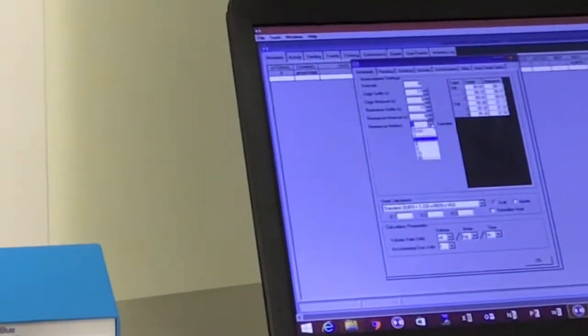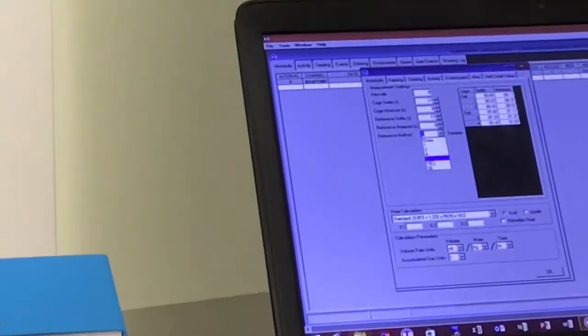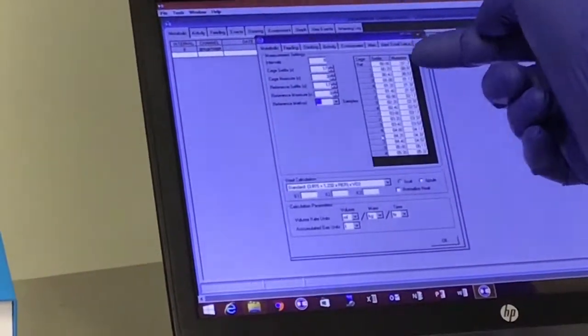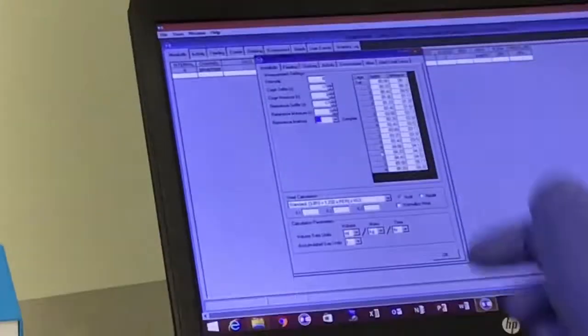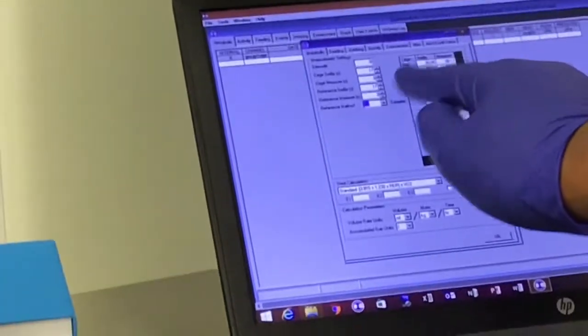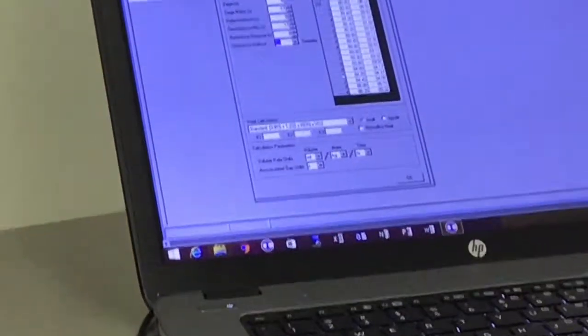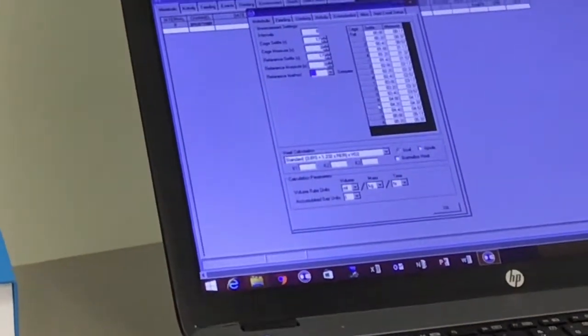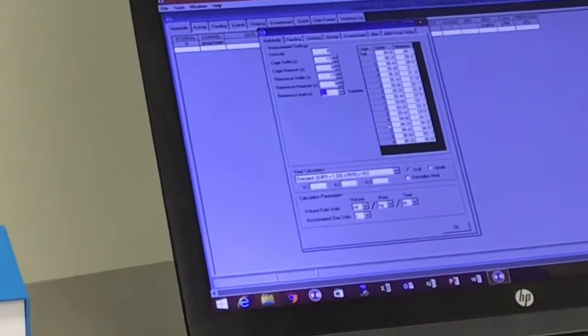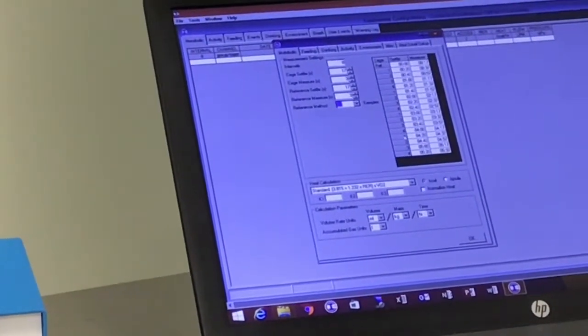Maybe I will pick a bigger number, reference every 16 sample. As you can see, it's 20 seconds per sample. So right now, every 16 samples it is going to read the room air, which means you will do room air. Cage 1, 2, 3, 4. Cage 1, 2, 3, 4. Cage 1, 2, 3, 4. Until 16 times, then it does a reference again.